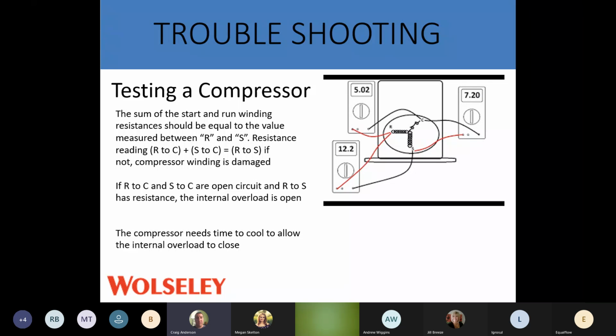So if we're checking from R to C, we're going to get a reading. And when we check S to C, we're going to get a reading. So those two readings added together should equal your R to S. If they don't equal, then we're looking at something going on with the windings in our compressor. If we're going R to C or S to C and we're getting an OL or something weird, or one of the windings is like 0.08, the other one's 8.3, you know you've got some windings that are in error. But those two should add up to your R to S.